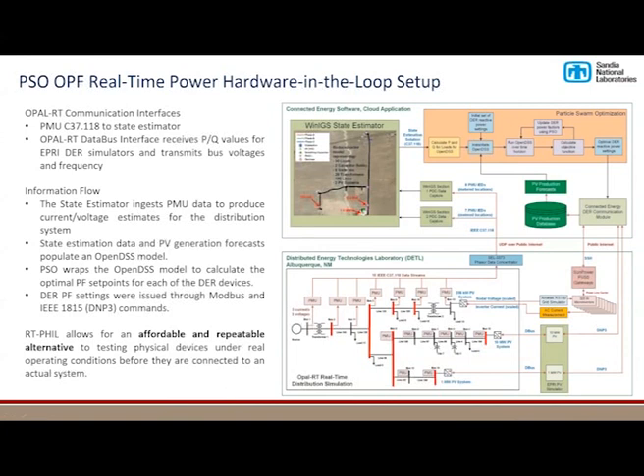Okay, so looking at how this works in the bigger scheme, on the bottom of the image here is DETL, our lab. Inside the OPAL-RT real-time simulation, we have a distribution system running. We've got PMUs connected to each of the buses there, and each of those PMUs are exporting C37.118 data streams to a physical SEL 3373 phasor data concentrator. That data is then exported over the public internet to our connected energy software vendor, which was running the Georgia Tech WinIGS state estimator. It completes the state estimation and exports that as another C37.118 stream to the PSO. We calculate the set points for the devices and then feed that back to the EPRI PV simulator, as well as our physical hardware-in-the-loop devices here. And so that's how you close the loop on the optimization.